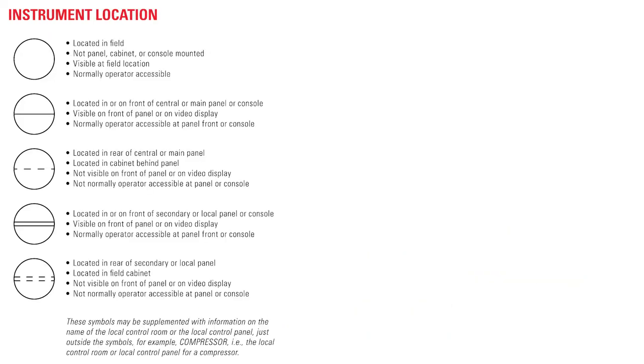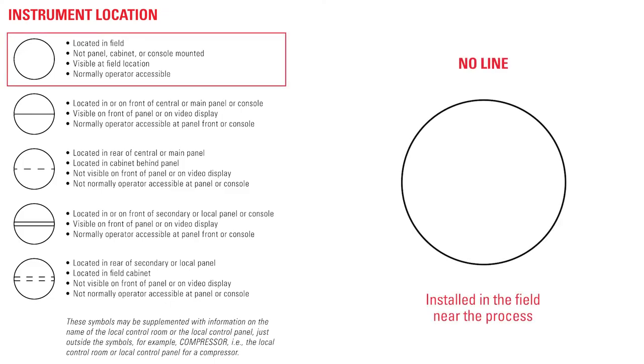The circle combined with the presence or absence of a line determines the location of the physical device. No line means the instrument is installed in the field near the process.